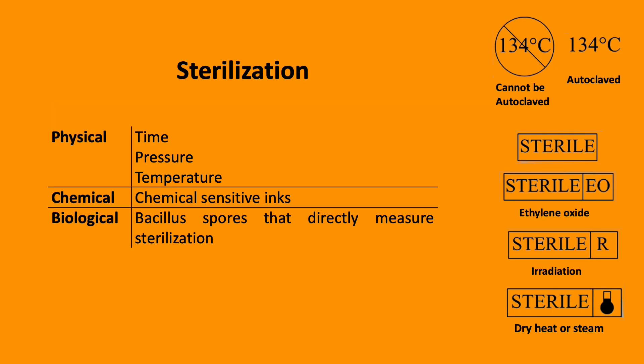It is essential to confirm that sterilisation is complete prior to using equipment on a patient. Therefore, physical, chemical and biological measures can be used to ensure this. Physical measures include adequate time, pressure and temperature monitoring during the process; chemical measures use sensitive inks; and biological measures use Bacillus spores that directly measure sterilisation. There is a range of key labels for sterility and autoclaving.